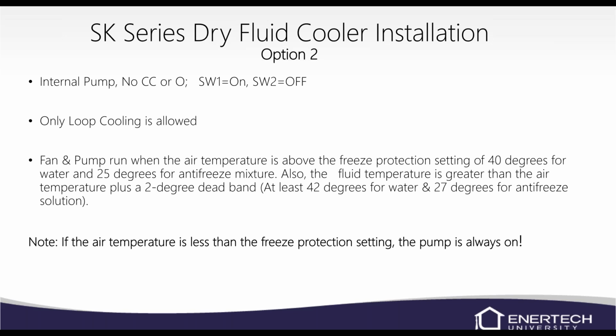And the fluid temperature is greater than the air temperature plus 2 degree deadband. Again, if the air temperature is less than the freeze protection setting, the pump will just stay on. Keep it from freezing up.